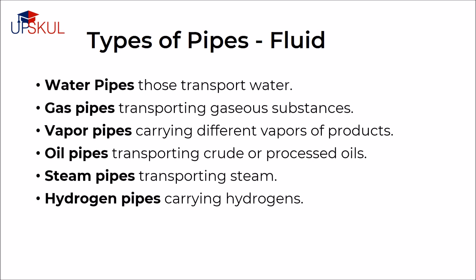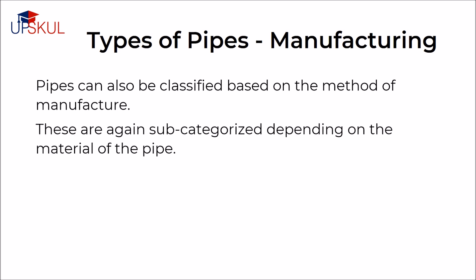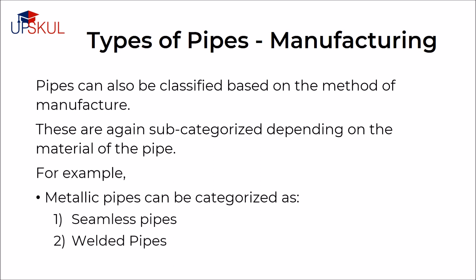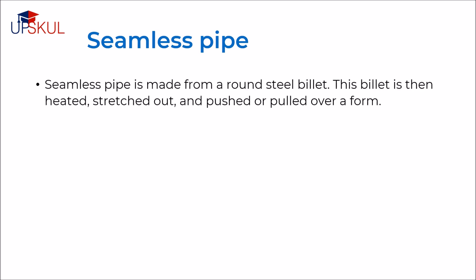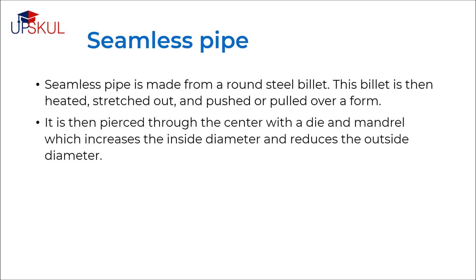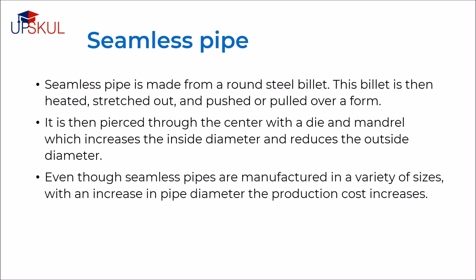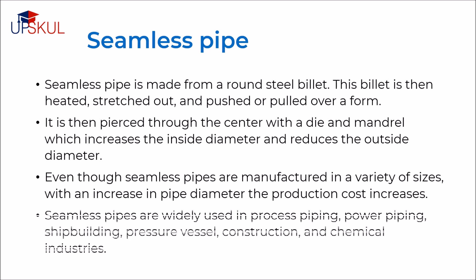Pipes can also be classified based on the method of manufacture. These are again sub-categorized depending on the material of the pipe. For example, metallic pipes can be categorized as seamless and welded pipes. Seamless pipes are made from a round steel billet, a solid cylindrical chunk of steel that is cast from raw material. This billet is then heated, stretched out and pushed or pulled over a form. It is then pierced through the center with a die and mandrel which increases the inside diameter and reduces the outside diameter. Seamless pipes are widely used in process piping, power piping, ship building, pressure vessels, construction, and chemical industry.